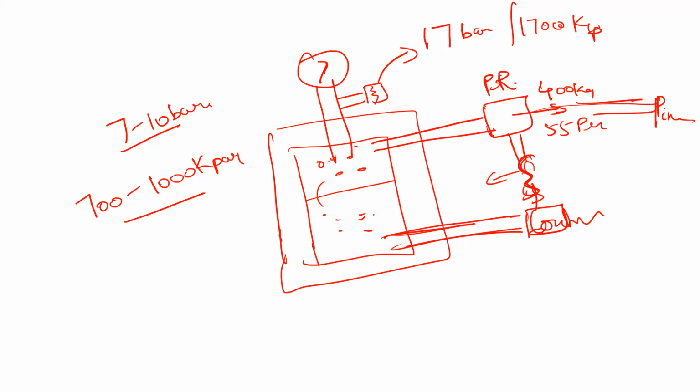Can you please explain the last one, the copper coil? Sorry? Control valve? Yeah, so there is another control valve here. When there is an excessive demand from the hospital, the vaporization rate might not be sufficient to match the demand. At that point, the control valve will open, draw away the liquid, and it is heated by the coil so that it gets vaporized fast, then it reaches the pressure regulator, then it goes to the pipeline. Okay, so got it. Right?